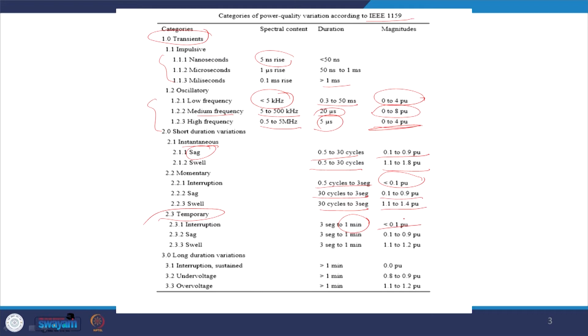Similarly, that is instantaneous, thereafter you may have temporary interruptions, the same way, 3 seconds to 1 minute per unit. SAG is the same way, 3 seconds to 1 minute per unit, SWELL is 1 minute per unit, and this will be the magnitude. And long duration variations, generally power interruption sustained for more than 1 minute, under voltage for more than 1 minute, and over voltage for more than 1 minute. Then we do not say it is SAG and SWELL, we call it under voltage, over voltage.